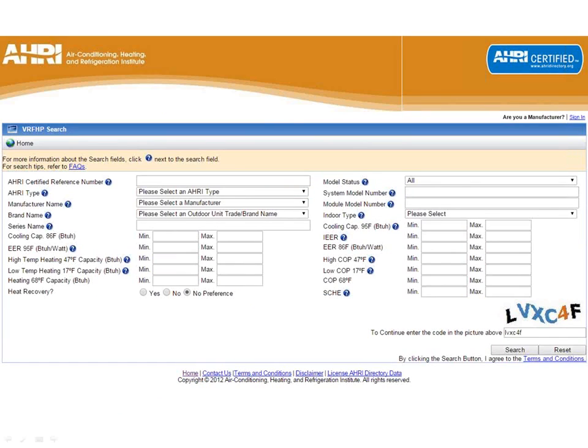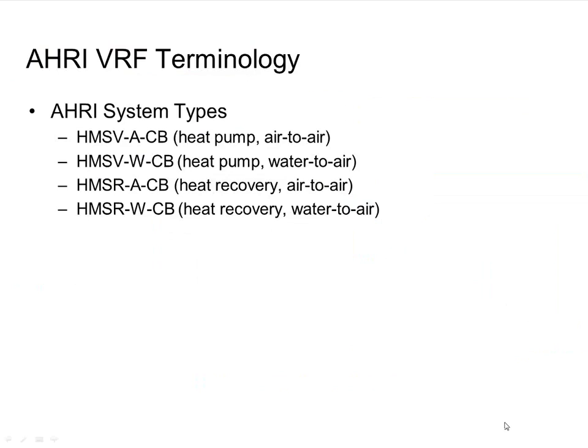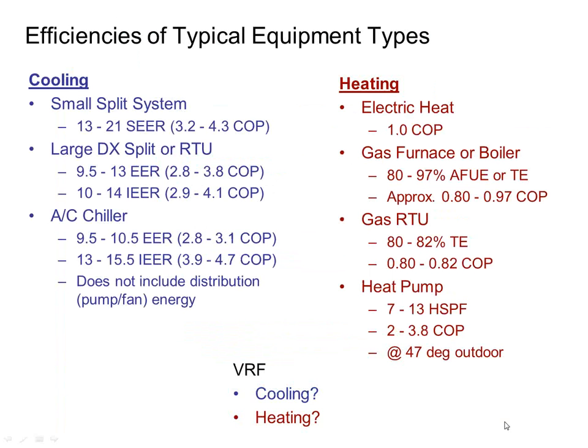Okay, before we go on to that, let me just address this electric resistance heat pump thing, because a lot of guys are typing questions in and they seem to be confused. All right, so some folks are arguing efficiency and COP, right, as a percent. A COP of 1.0 is the same as 100% efficient. A COP of 2.0 is 200% efficient. A COP of 3.0 is 300% efficient. COP is just a direct ratio of how much energy did I bring in versus how much capacity in terms of energy did I get out.